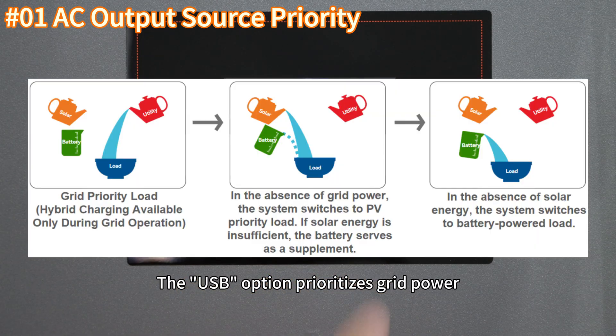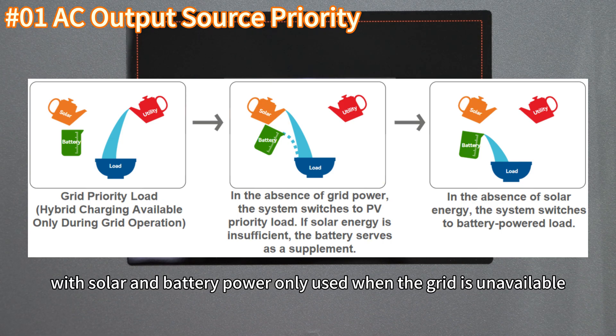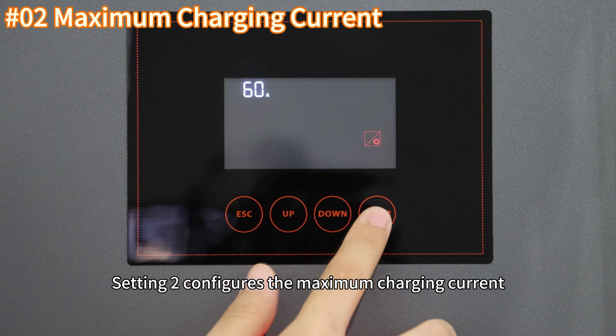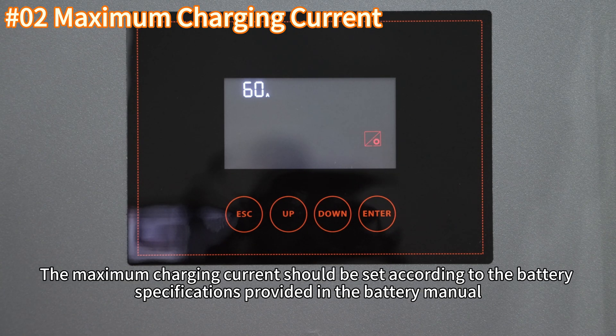The USB option prioritizes grid power, using it as the primary source for load supply, with solar and battery power only used when the grid is unavailable. Setting 2 configures the maximum charging current, which includes both grid and solar charging current. The maximum charging current should be set according to the battery specification provided in the battery manual.